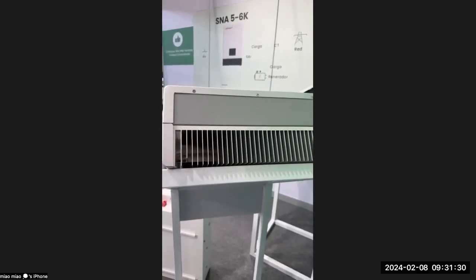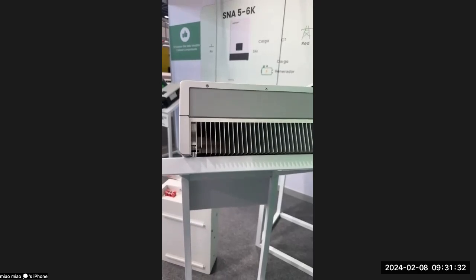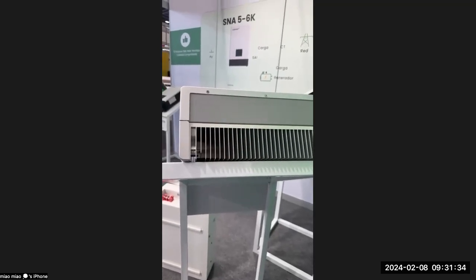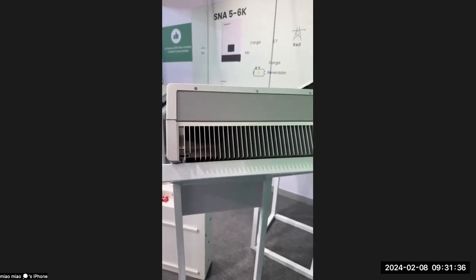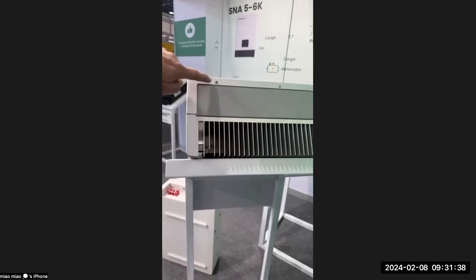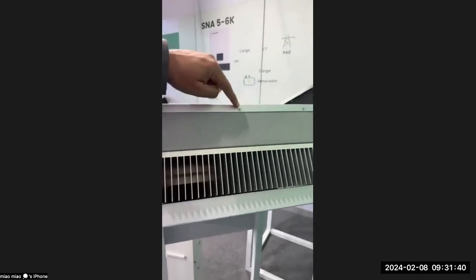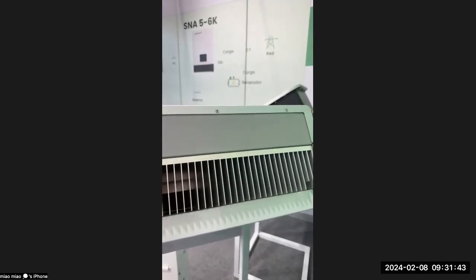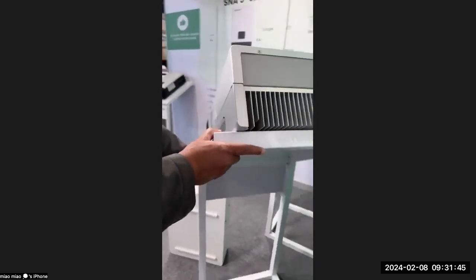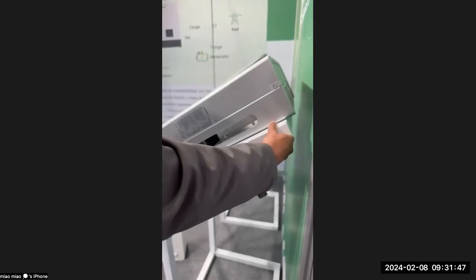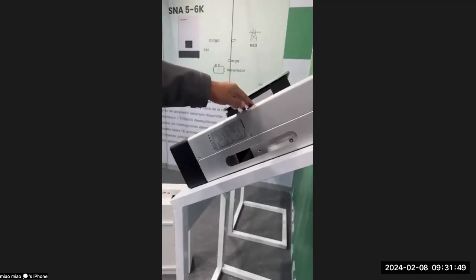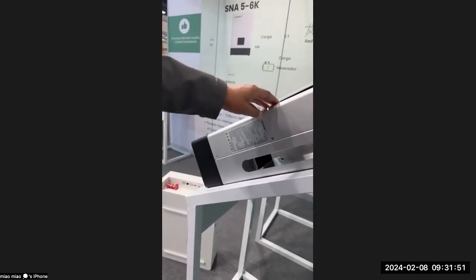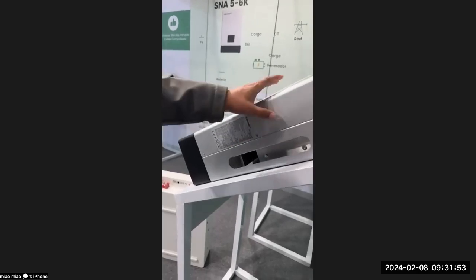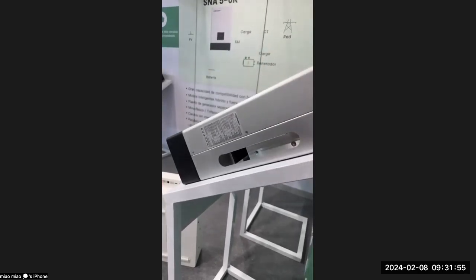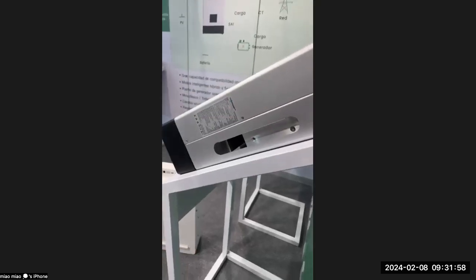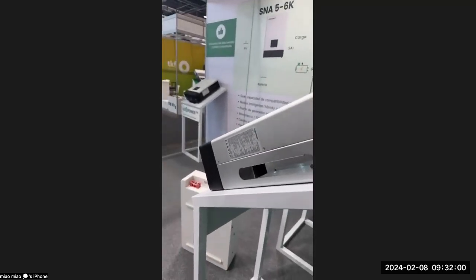If ever you need to put it into an application where the humidity is high or it's a high dust environment, or even outdoors, this is going to be the machine for you. Right, even down to the screws are corrosion resistant screws. And all in all, it's a very, very robust machine. The only drawback about this machine is the fact that on EPS, it can only put out 4 kilowatts on battery.